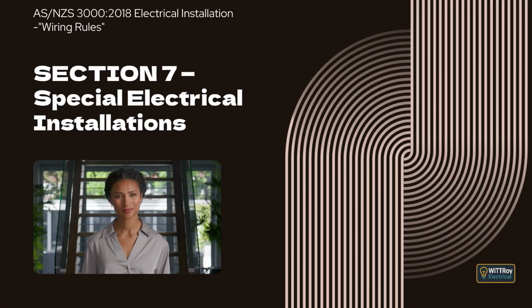Clause 7.4.8.1, General. This clause explains that in addition to Section 8 testing, the separation of each separated circuit must be individually confirmed. It explains that separation is verified by measuring insulation resistance between the separated circuit and the transformer primary winding where applicable, other wiring, other separated circuits, and earth. It explains that insulation resistance must not be less than 1 megohm when tested at 500 volts direct current.